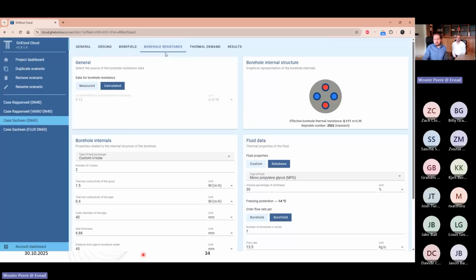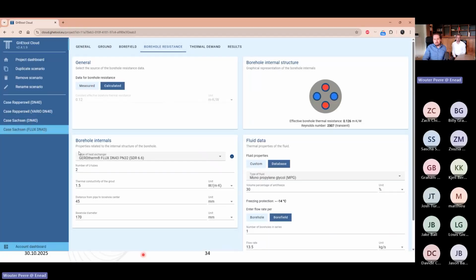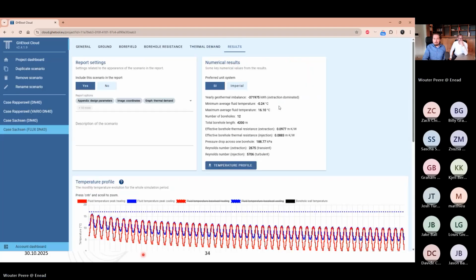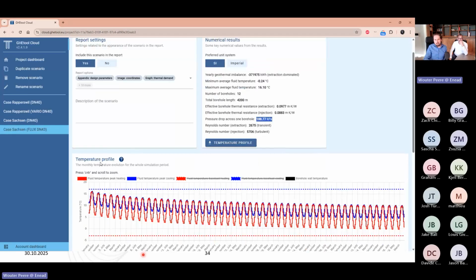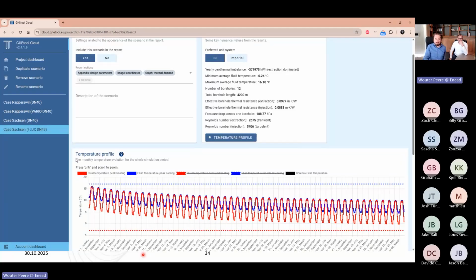Now, if we go to our borehole resistance step and change it to the GEROtherm FLUX probe, the DN43 PN32, all the parameters stay the same. We see here again that our average temperature is a little bit higher. Our borehole resistance is a little bit better, which I explain because the wall thickness is on average a little bit smaller. But what is important is that our pressure drop is now significantly lower. We came from 540, and we are now at 190 kPa.